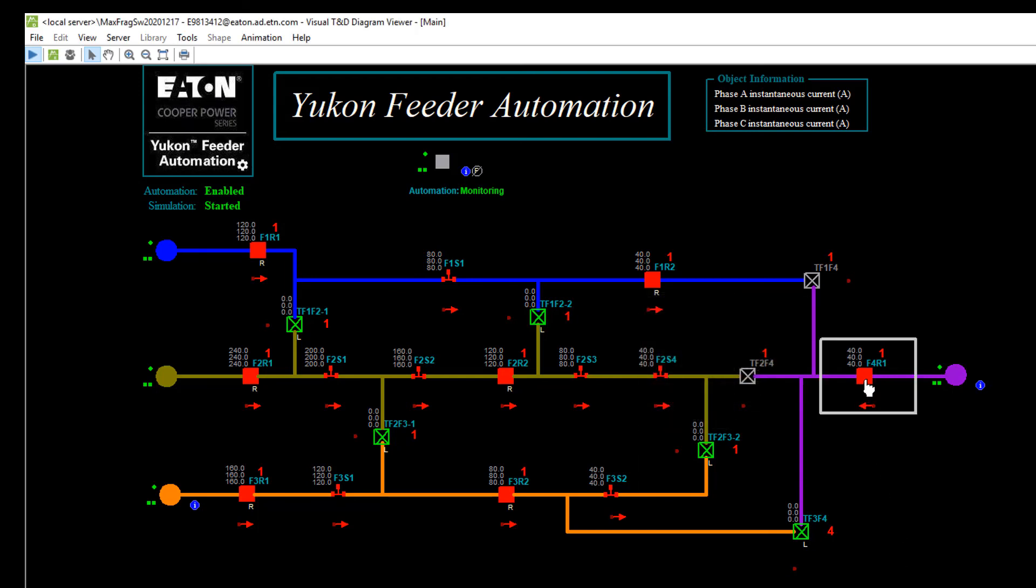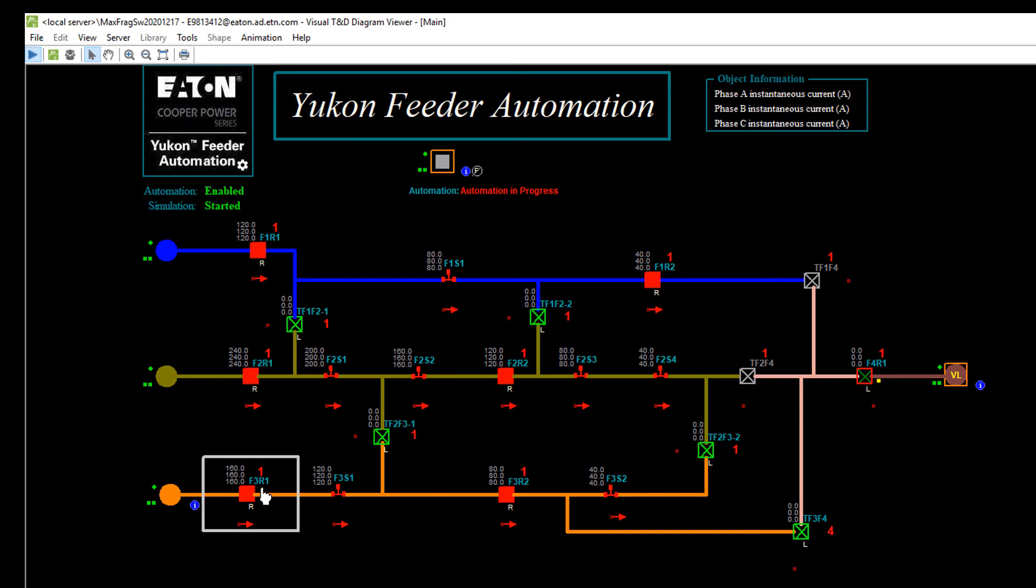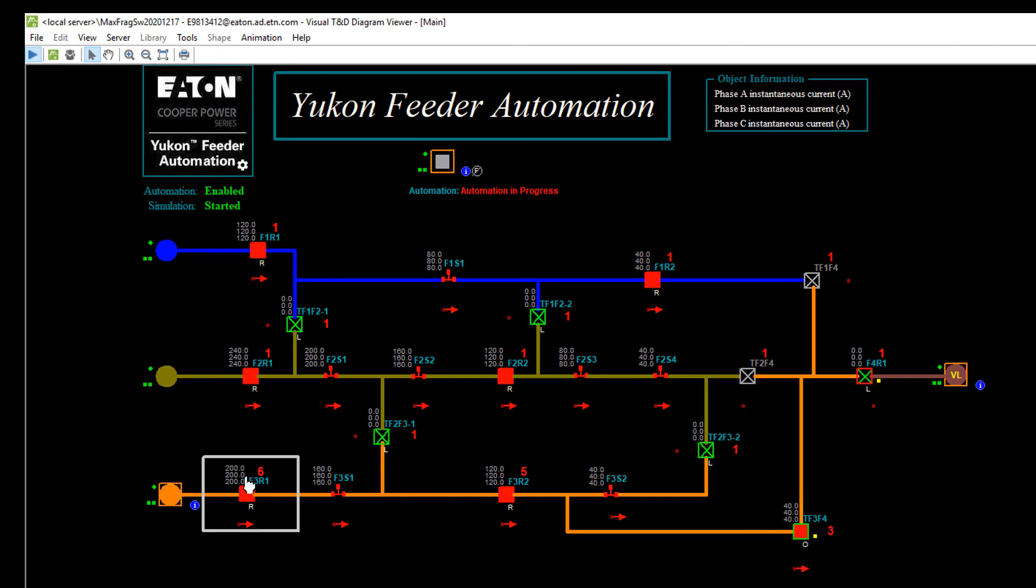YFA should open this device, and now we should see these upstream devices change profile before it closes in, and then we expect this one to become a three. I expect these to transition to a five. We'll close that guy in, and then they'll transition to a six, and that's what they did. And then this normally open point, because it's fed off of feeder three, now transitioned to a three.